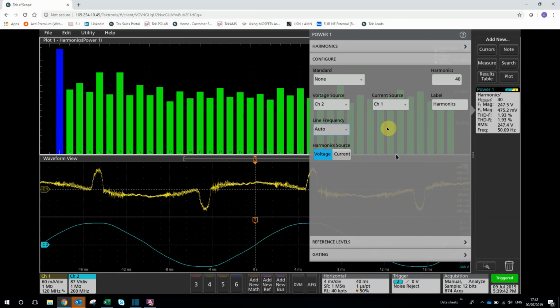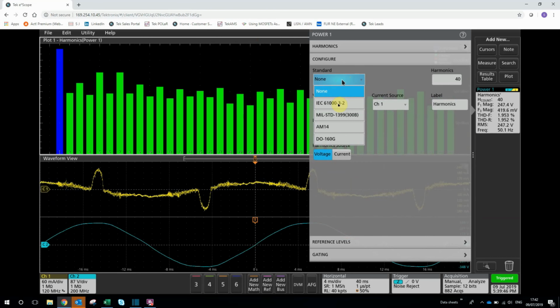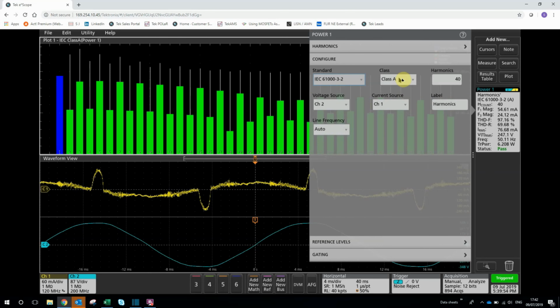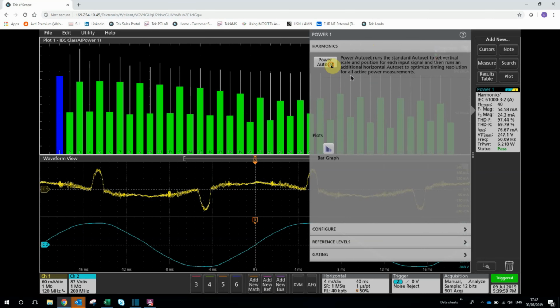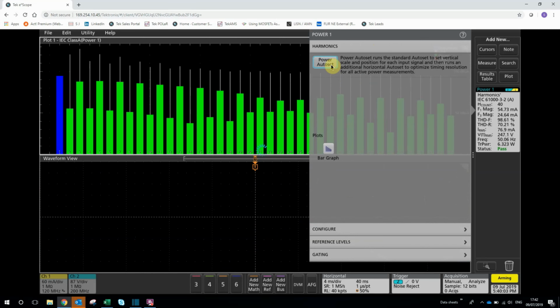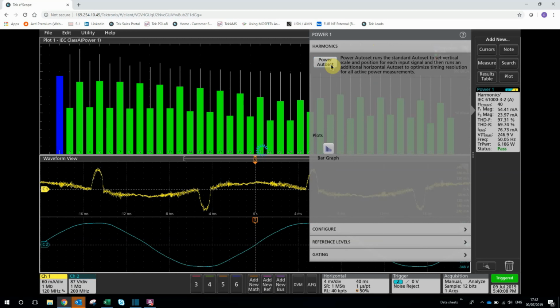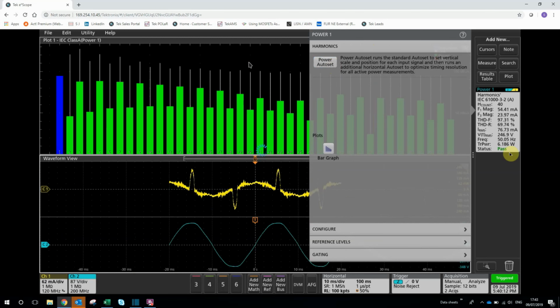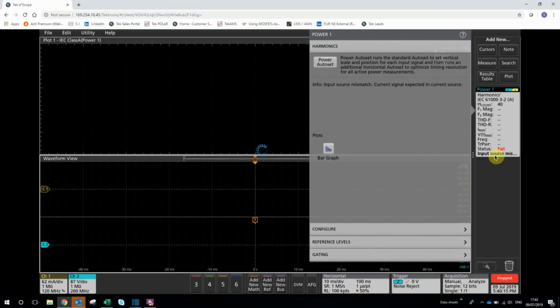We're going to test this particular power supply against an electrical standard. So we'll select the IEC 61000-3-2 standard, and we'll test against class A of that for this measurement here. So coming back to the top and pressing power auto set, sets the scope up in terms of record length and channel gains to make sure that we get an accurate measurement against that standard. So there we go, the scope's done its job, and we're getting some results there.